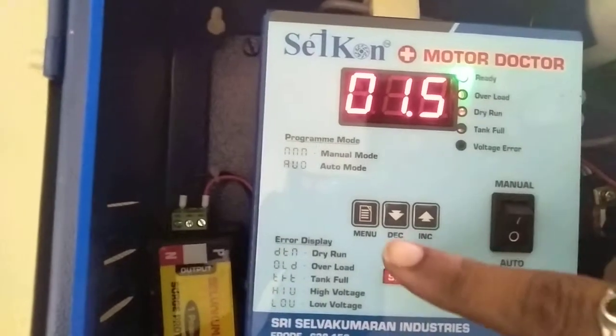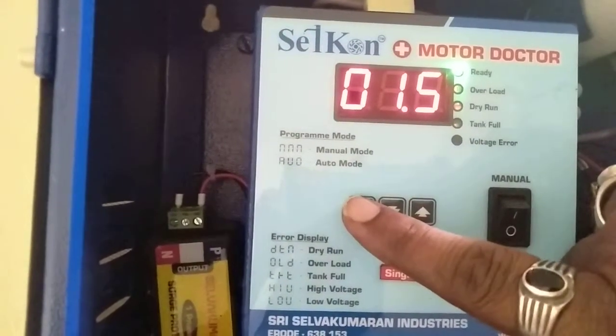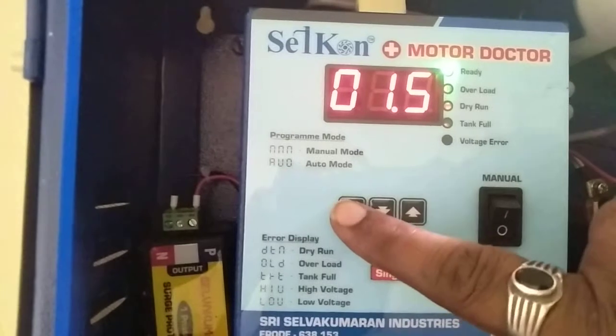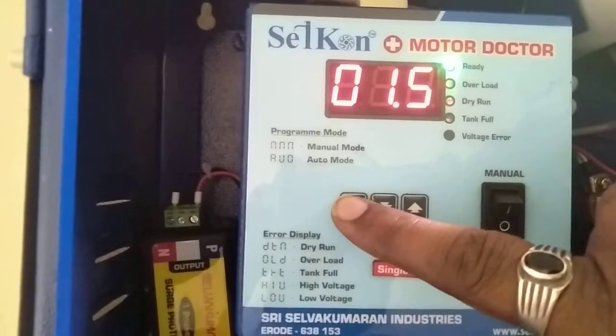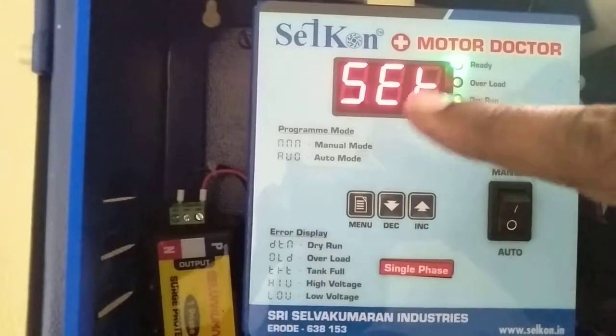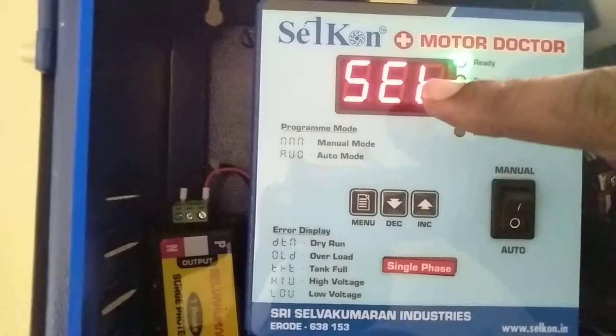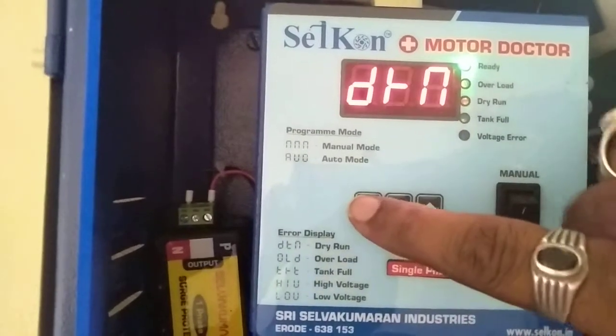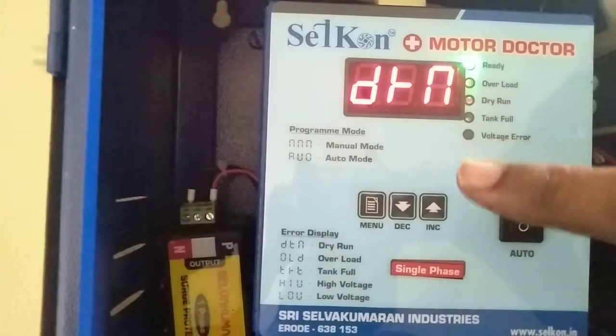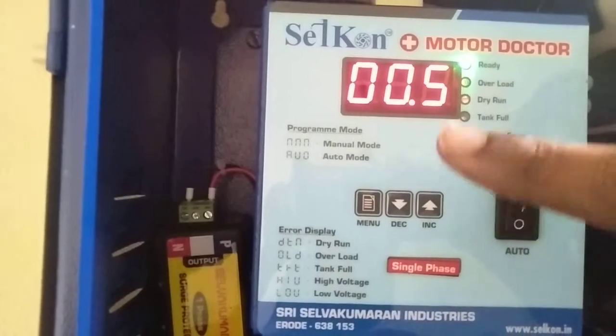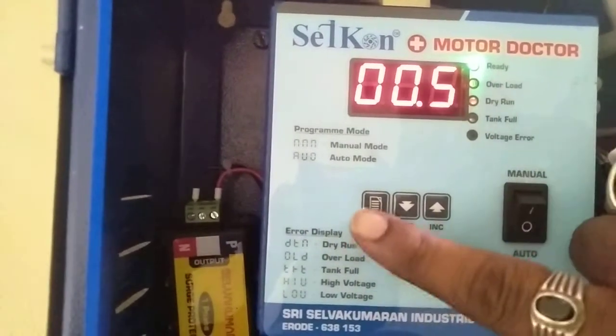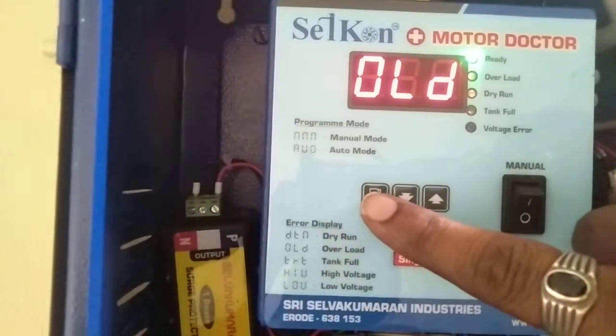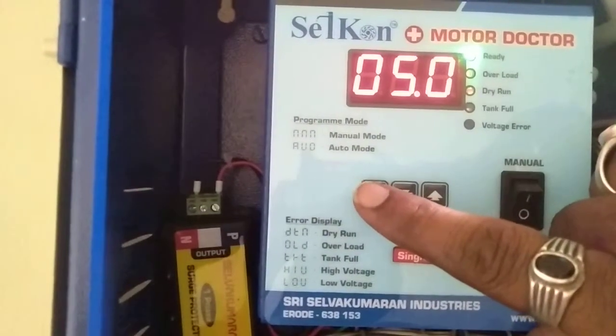So now let's see what the functions in the menu are. Just press the menu button for 3 seconds. Once you press it for 3 seconds, the display changes. That is SET. Now you press once again. There is dry run, DRN. Dry run: we have already fixed 0.5 amps as the dry run. Then you press the menu, overload. Overload is already set as 5 amps.